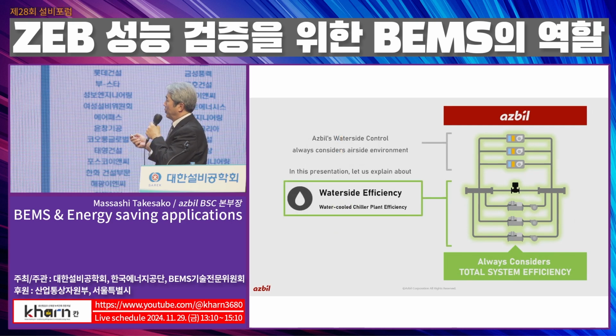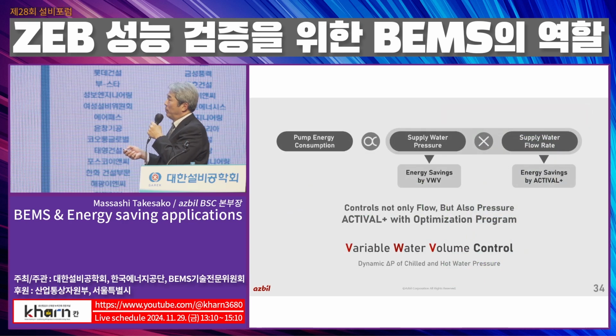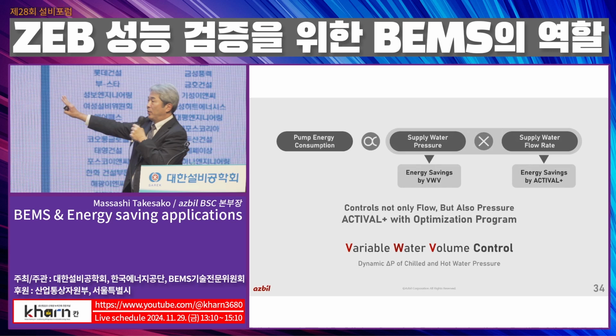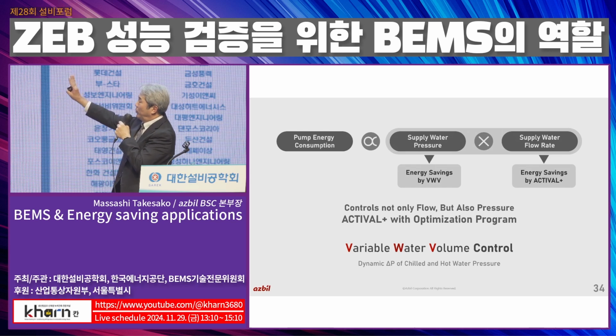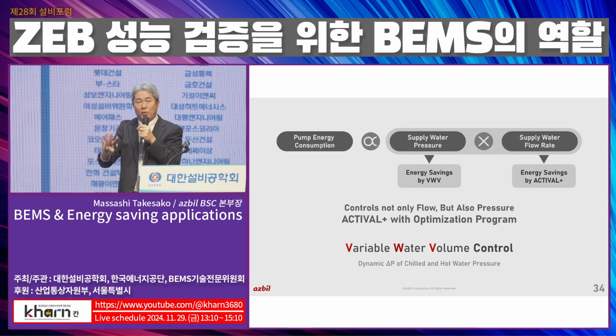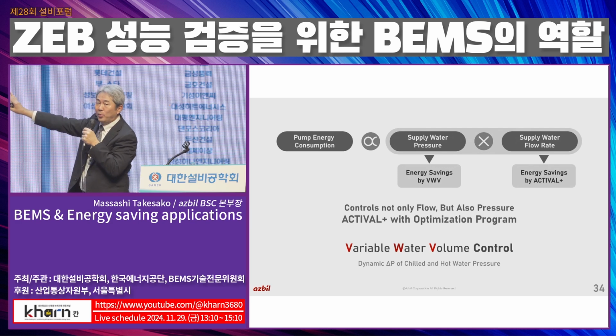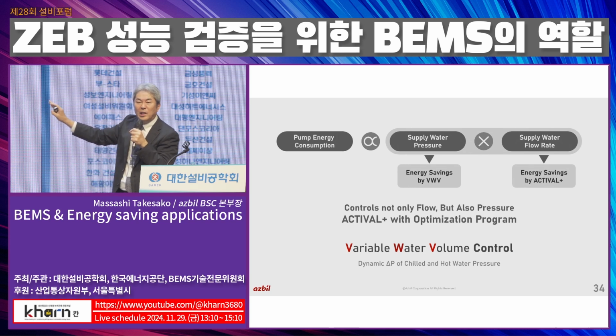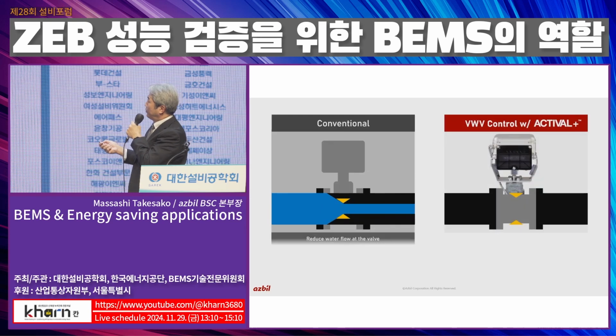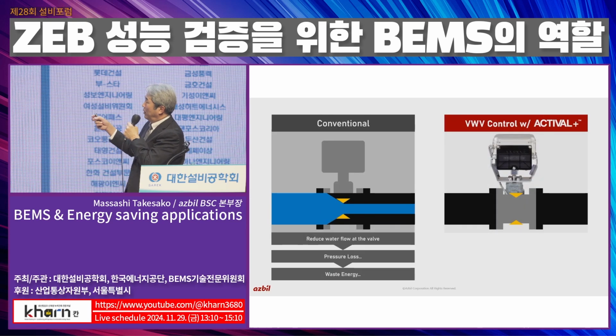Then from here, I would like to talk about water side efficiency, meaning pump efficiency. Pump energy consumption is very simply pressure multiplied by water flow. Once we implement the VSD on the pump, water flow can be reduced very easily. But the point is how we can reduce the pressure. This is the key to maximize the benefit of the VSD. Okay, so this is our control concept.